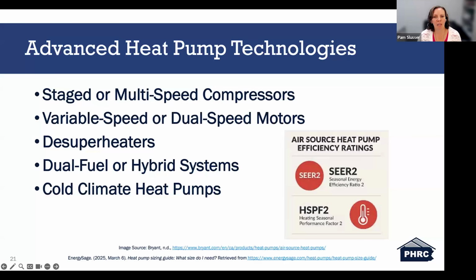And then there's the desuperheater. These are some high efficiency heat pumps. They're equipped with a desuperheater, which recovers waste heat from the heat pump's cooling mode and uses it to heat water. These heat pumps can heat water 2 to 3 times more efficiently than an ordinary electric resistance water heater. So in many cases, you don't have an electric hot water heater. Your hot water heater also works off of your heat pump due to this technology.